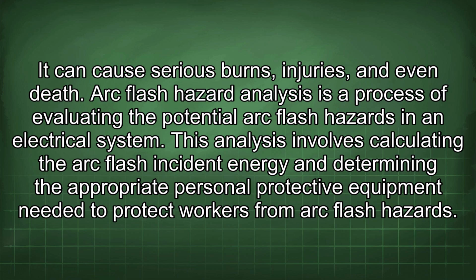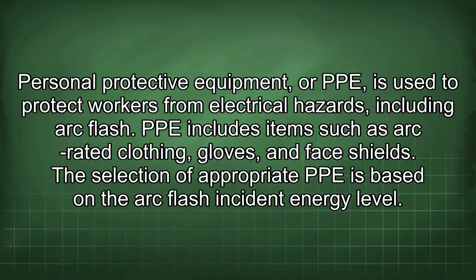from arc flash hazards. Personal protective equipment, or PPE, is used to protect workers from electrical hazards, including arc flash. PPE includes items such as arc-rated clothing, gloves, and face shields. The selection of appropriate PPE is based on the arc flash incident energy level.